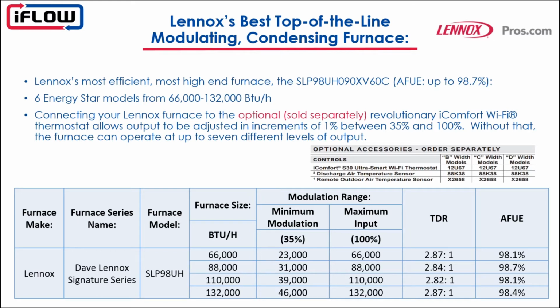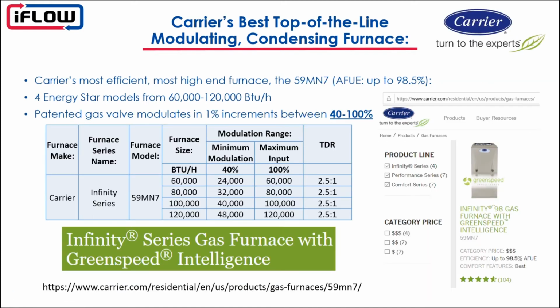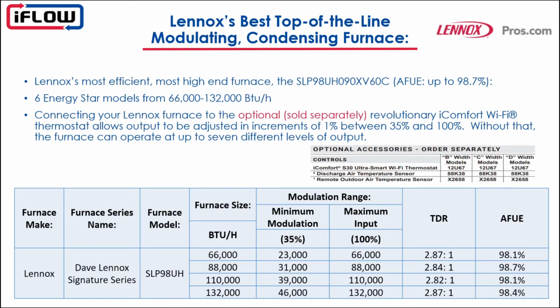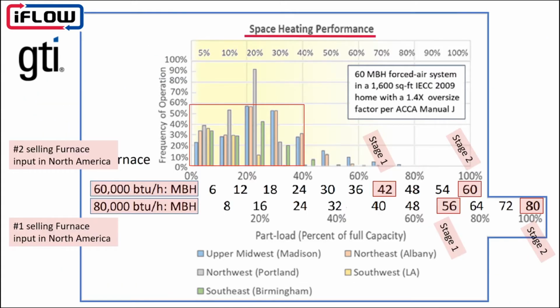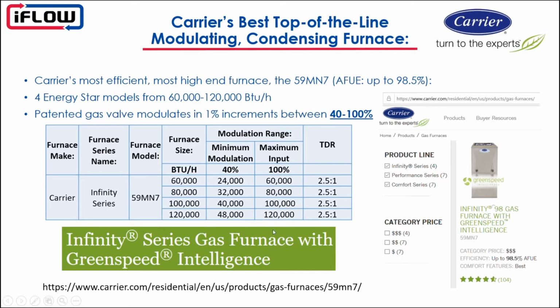If the heat loss is, as we see in the distribution, below 24,000 BTUs, this 23,000 BTUs really isn't going to help us much. So even this Carrier furnace and this Lennox furnace, both top of the line and would be great furnaces if sized properly for the home. But in the distribution we were looking at, they may not help us much, because the range in which we need the modulation, 0 to 24,000 BTUs, we really aren't able to achieve with either of these newer furnaces.